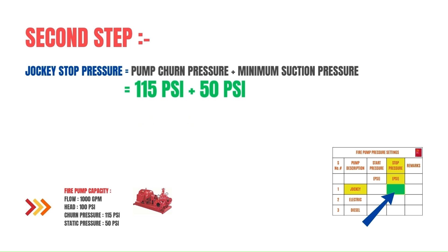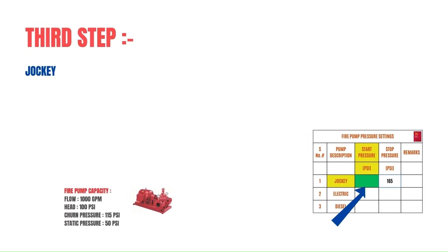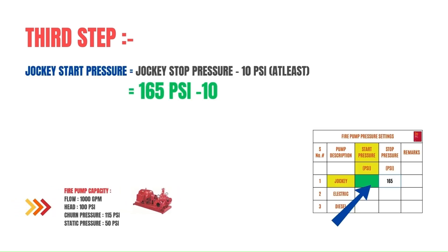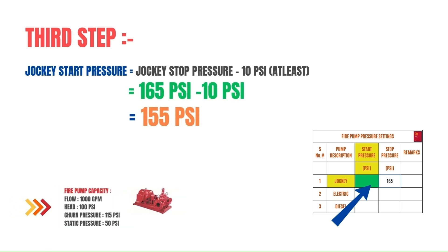After calculating the jockey stop pressure, we move to the third step: calculating the jockey pump start pressure. The jockey pump start pressure will be the jockey stop pressure minus at least 10 psi. So from our data: 165 psi minus 10 psi gives us 155 psi.